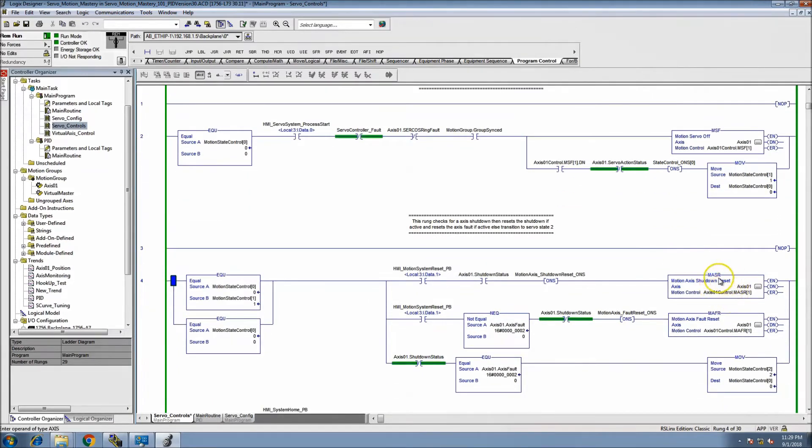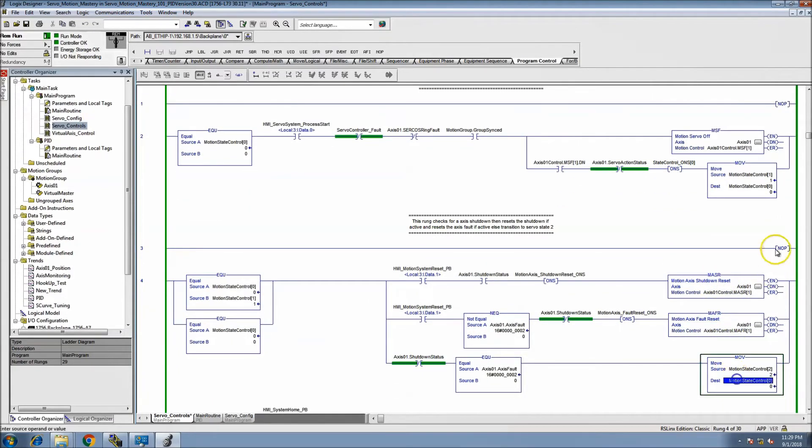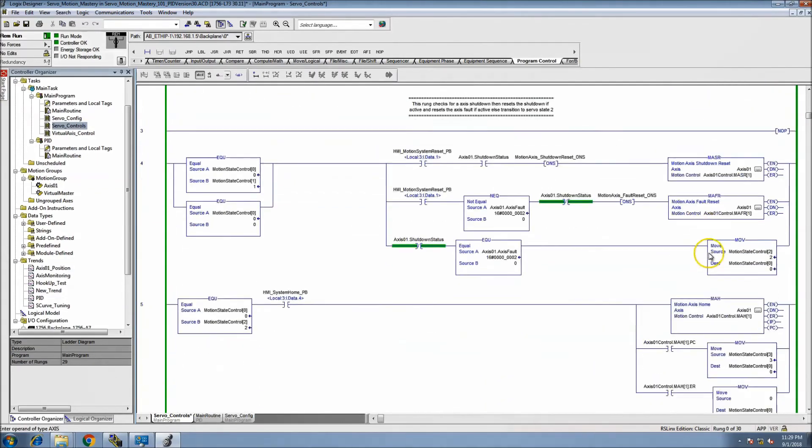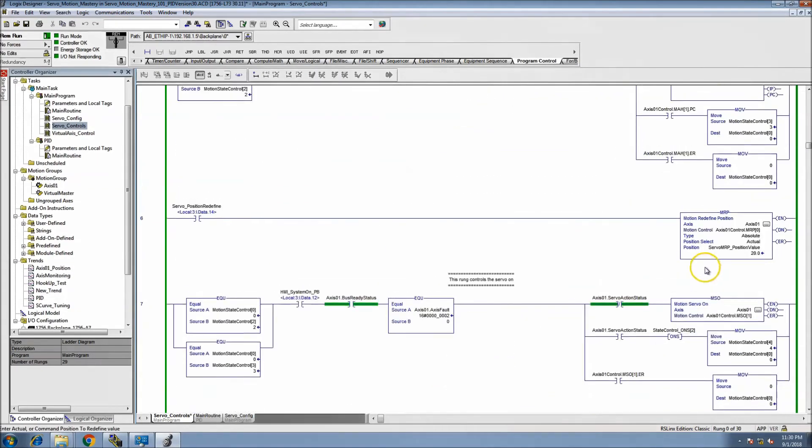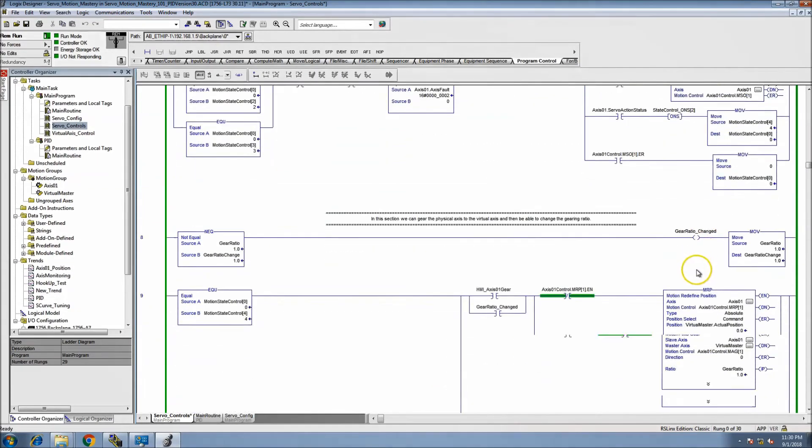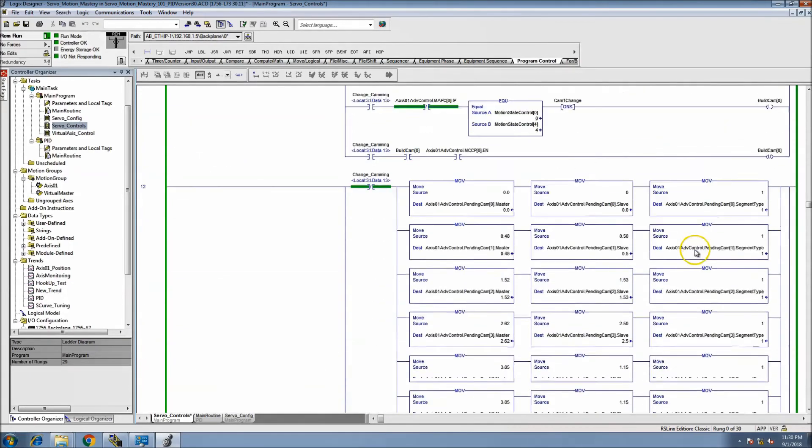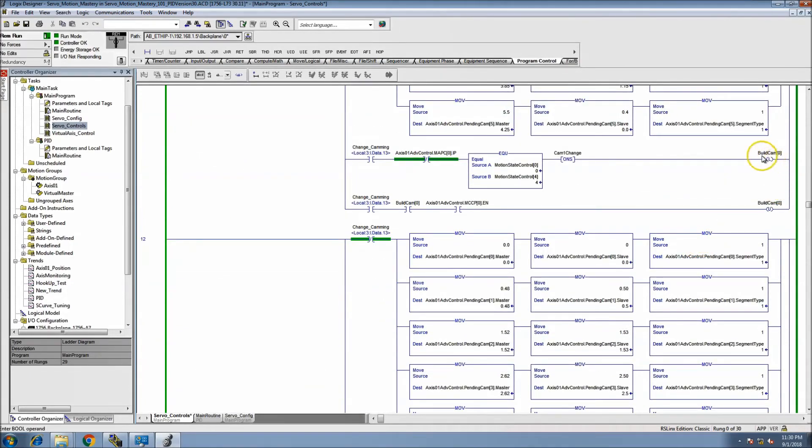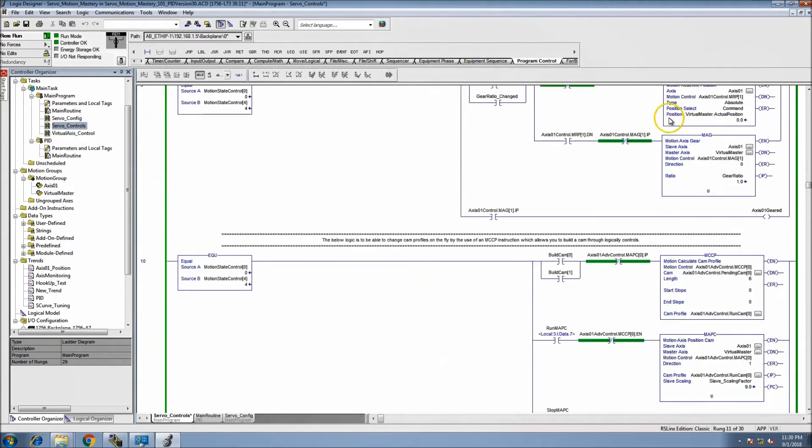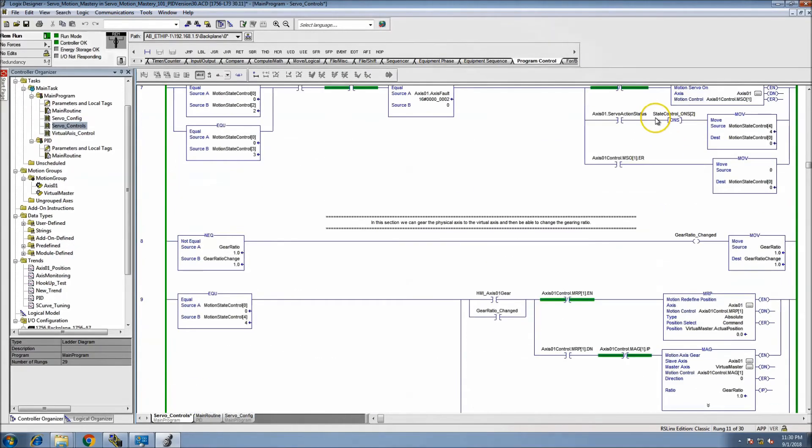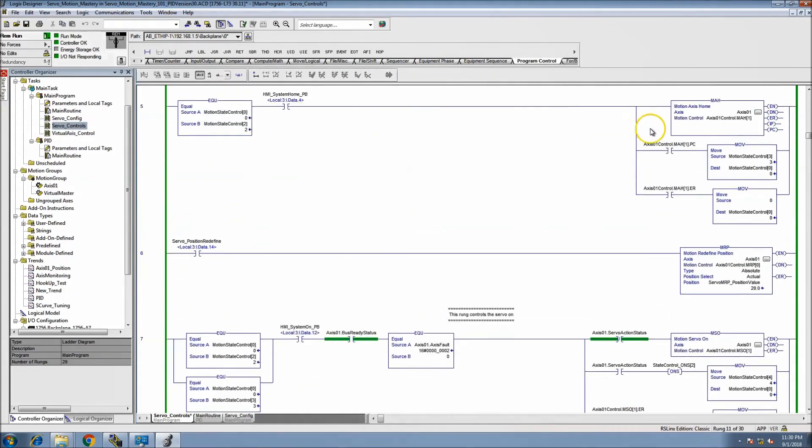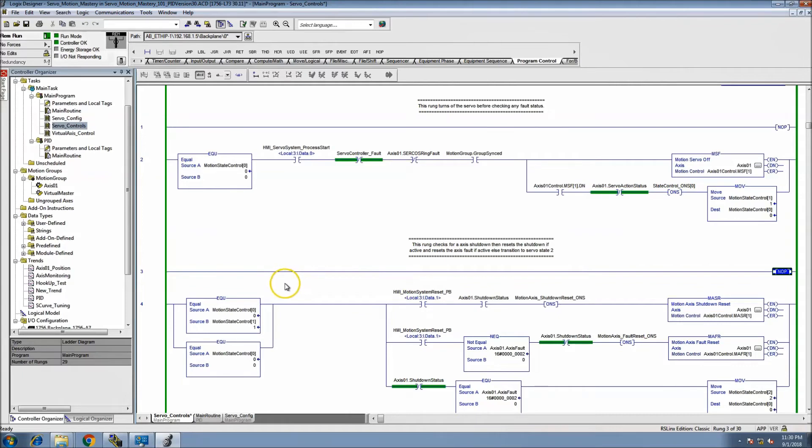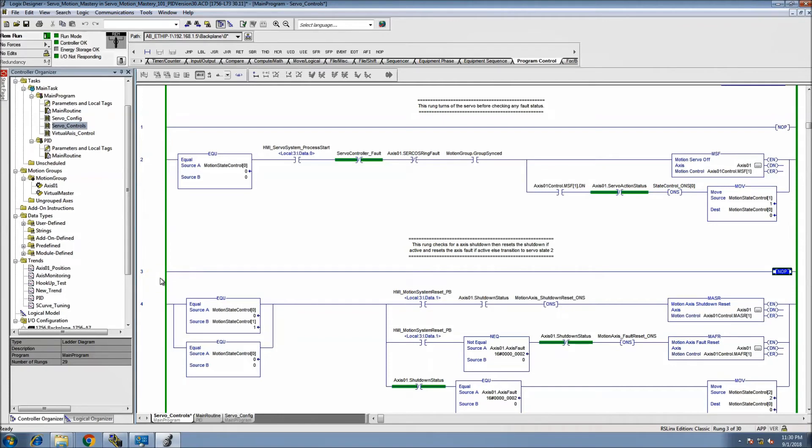You don't need an instruction or an output, whether it be an OTE or OTL. You don't need that. The no operation serves as that, and it just tells the processor that it's a point of reference or a point where you, as the programmer, have put in a note or a place to interrupt the program. It's not necessarily a break because it still scans it, but it's a point of interruption.